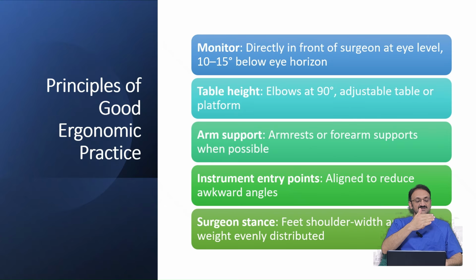If the monitor, for that matter, is really very high, and the surgeon is short and the tower is high, so he'll be looking like this. This will lead to fatigue as well. So the monitor should be directly in front of the surgeon, not towards one location, and it should be 10 to 15 degrees below eye horizon. So my laptop here is lying in a comfortable position. I'm looking down on the monitor rather than looking up towards the screen. So this is the comfortable position for the eye.